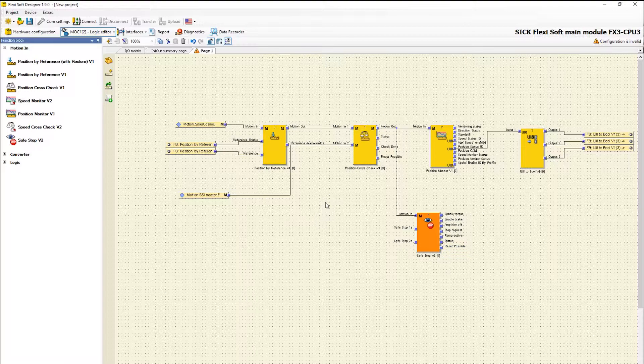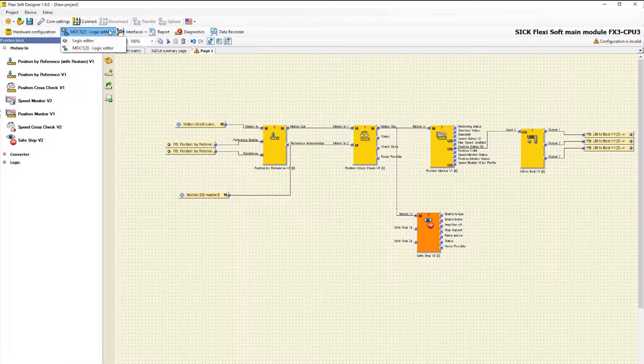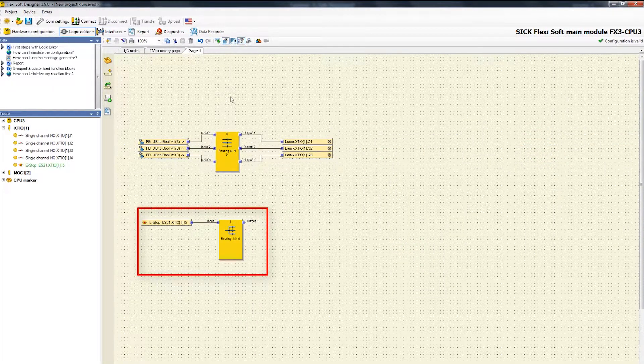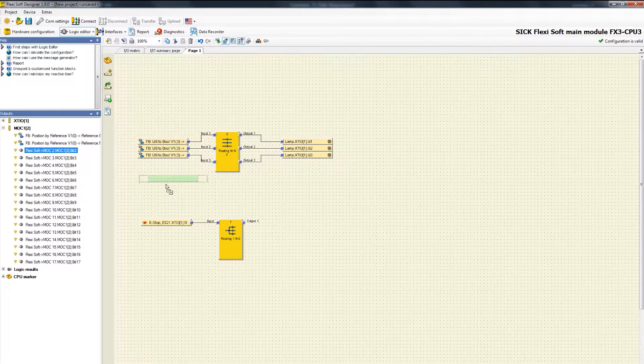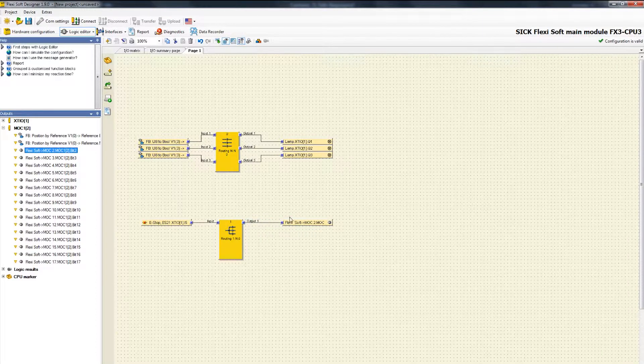Because the function Safe Stop 1 is executed normally after an e-stop was pressed, we have to route the signals of an e-stop from the CPU to the MOC1. Therefore we switch to the CPU logic, where I have already connected an e-stop to a routing end-to-end function block. Now we have to switch in the left sidebar to outputs, where we take bit 2 and connect it to the e-stop.